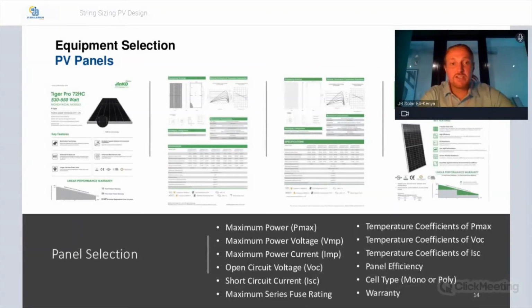So you need to consider the maximum power, that's P max, the wattage of the panels. But also the maximum power voltage, which is VMP, the maximum power current, IMP, the open circuit voltage, the short circuit current, and the maximum series fuse rating. That's important if you're going to use a Y branch connector.